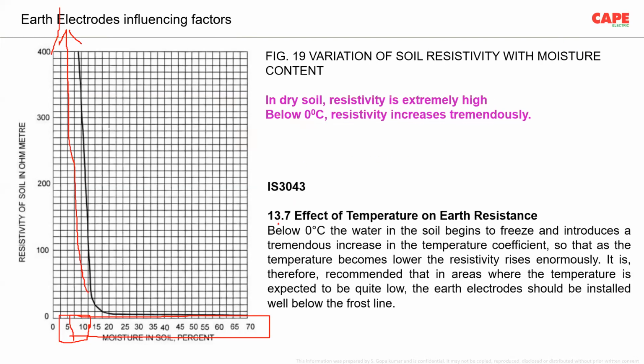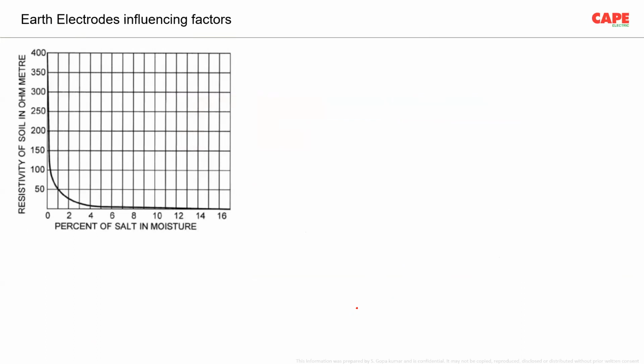In IS 3043, clause 13.7 says that below 0 degrees centigrade, the water in the soil begins to freeze and introduces a tremendous increase in the temperature coefficient, so that as the temperature becomes lower, the resistivity rises enormously. It is therefore recommended that in areas where the temperature is expected to be quite low, the earth electrode should be installed well below the frost line. How deep is well below the frost line is a big question. We will discuss it later.